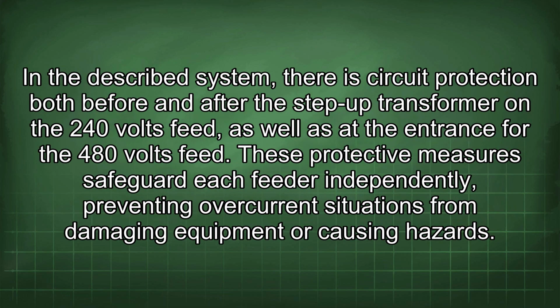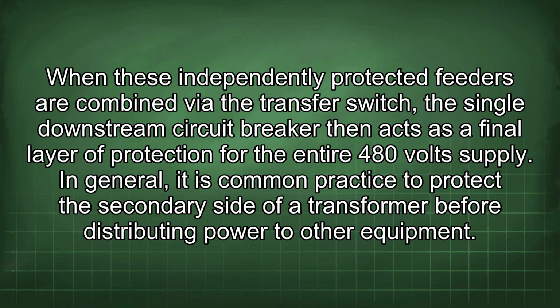In the described system, there is circuit protection both before and after the step-up transformer on the 240 volts feed, as well as at the entrance for the 480 volts feed. These protective measures safeguard each feeder independently, preventing overcurrent situations from damaging equipment or causing hazards. When these independently protected feeders are combined via the transfer switch, the single downstream circuit breaker then acts as a final layer of protection for the entire 480 volt supply.